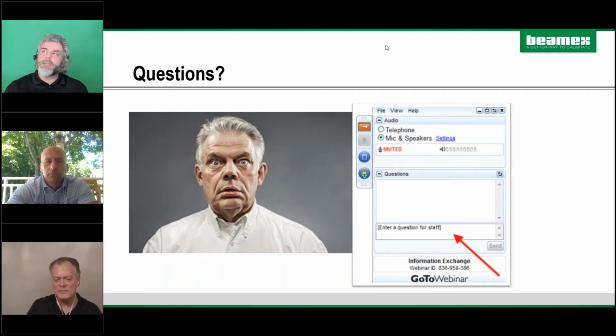So that's a good goal, is not to calibrate it if it's not malfunctioning. With that, there are cases where it doesn't matter what the exact temperature is, you just need to know that there's temperature for this item on the loop. I've seen some cases where going from calibrating it annually to a run-to-failure approach, meaning we're not even going to calibrate this because it's not critical to the process whatsoever. Maybe it's an ambient temperature thing that's a comfort level for a controller, but it just doesn't matter, so you run it till it fails and then you replace it. So I think the answer depends on the criticality of what you're actually looking at, criticality to the process, on whether you should calibrate it and how often.